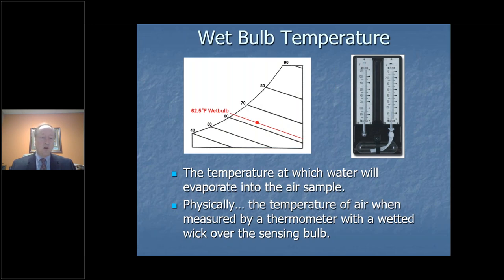You would go to the curve that's on the top left of the chart and you would find 62.5 Fahrenheit wet bulb. And then you would follow that diagonal line. And where that line intersects the 75 degrees that we had right here earlier, that is now your state point. That will tell you all of the other conditions that you want to know about the environment in which you are trying to work.